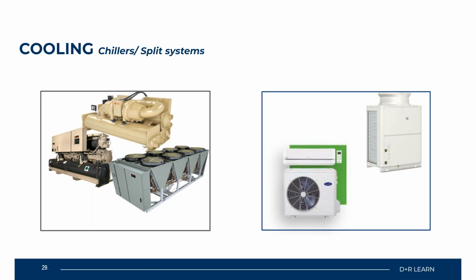It'll have enough capacity to do so, because you're literally pumping chilled water constantly through the coils that are in that server rack within its heat exchanger. So it's a really sweet system, and these chillers are great at doing that as far as air-cooled chillers are concerned. Now, your water-cooled chillers, same type of cooling delivery you'll get from both systems. But your water-cooled chillers are a lot larger than your air-cooled chillers. These systems have the capacity in the thousands of tons.